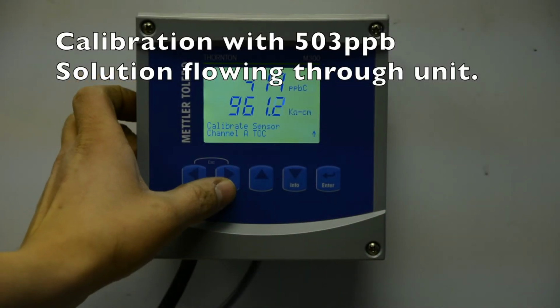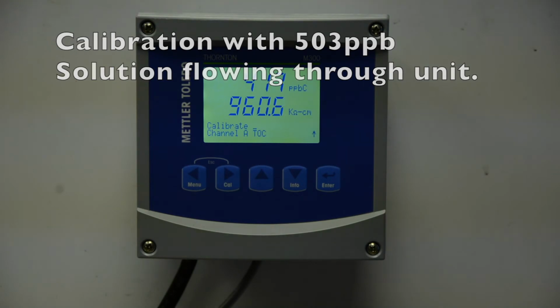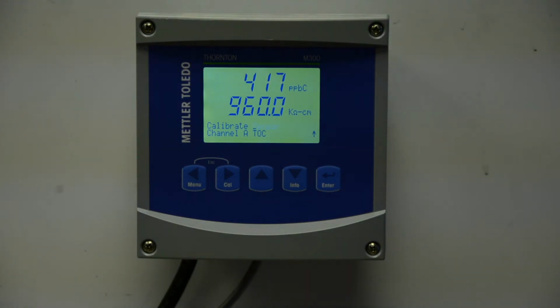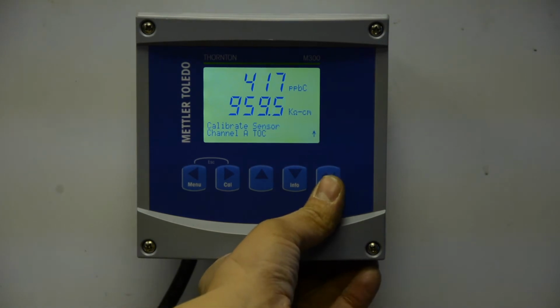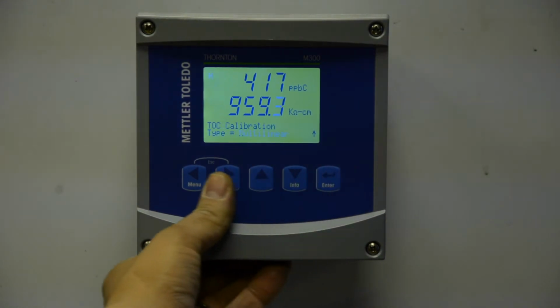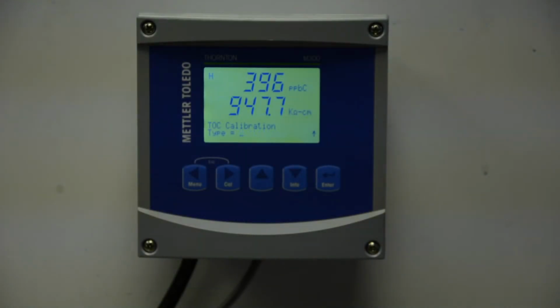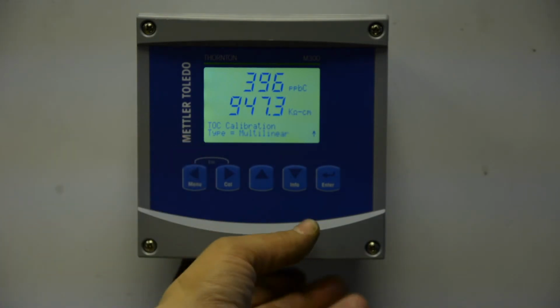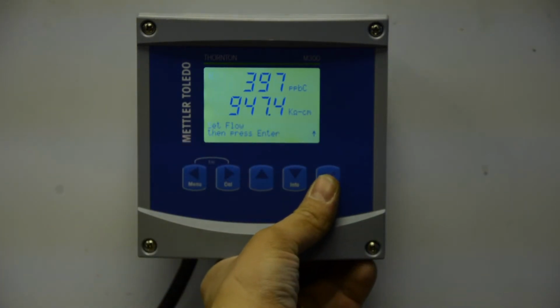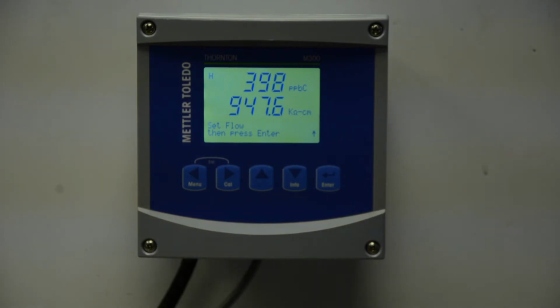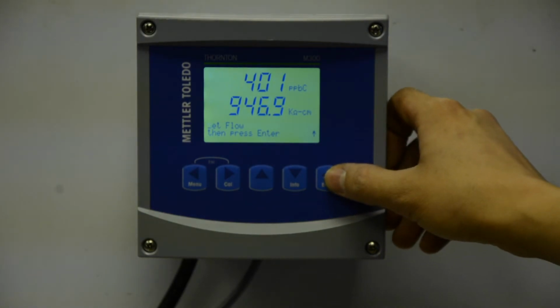Go into Calibrate, into your M300, and it'll ask you whether you want to calibrate the sensor or it gives you other options. We're going to calibrate the sensor, so hit Enter to calibrate the sensor. With this calibration, we want to perform a multilinear calibration. So we will go into Type, Multilinear, and hit Enter. Now it's going to ask you to set your flow and then readjust your meter so that you can check your flow. Verify that your flow ratio is correct. If not, you need to adjust it until all 4 lights are lit. Once it's properly adjusted, press Enter.